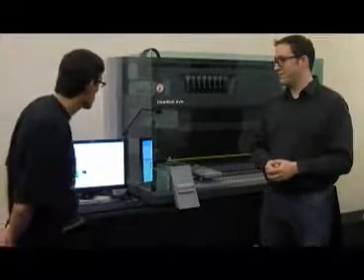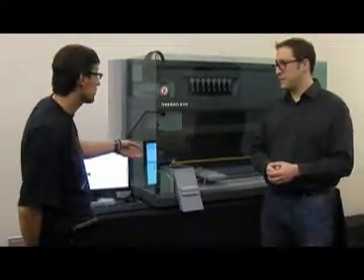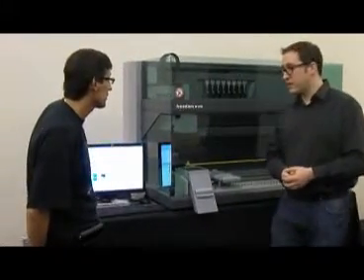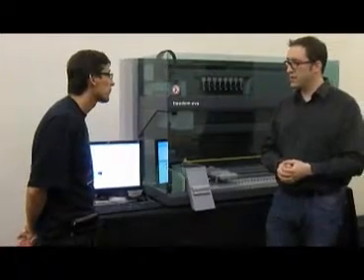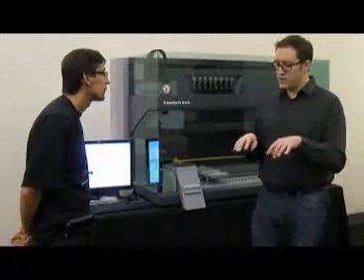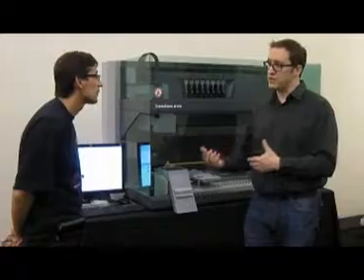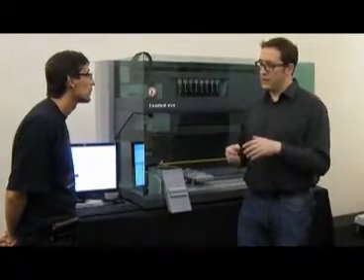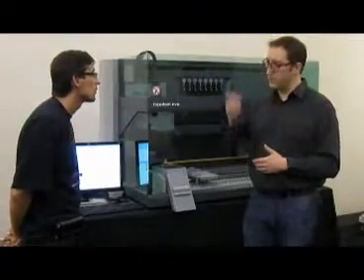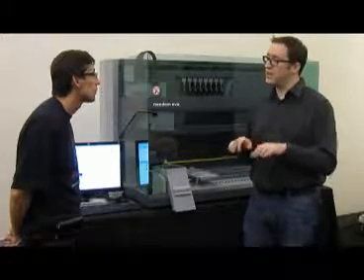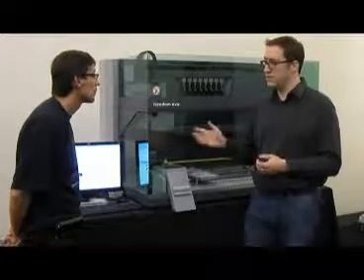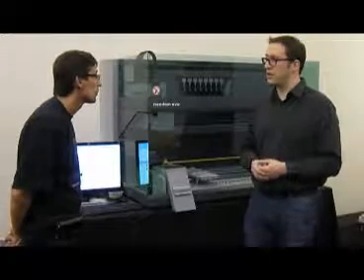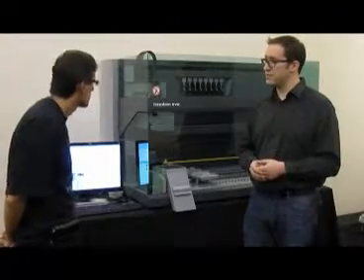A lot of the users will learn about that, because I think you have a couple of different sensing technologies. We do have several. This one here has the capacitance liquid level detection, so each finger we can spread out so we can access tubes all at the same time. And the channels can move independently in Z, so they can move up and down on their own, and detect the surface of the liquid, either through capacitance, like this arm here, or through pressure, with our pressure monitor pipetting options.